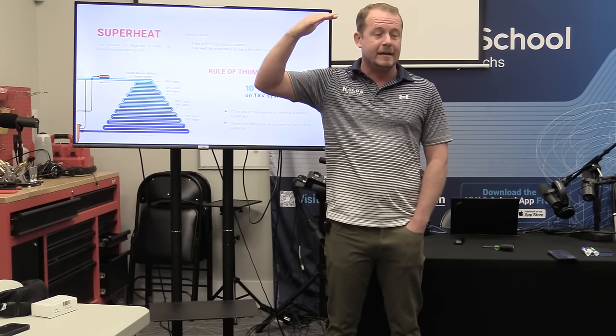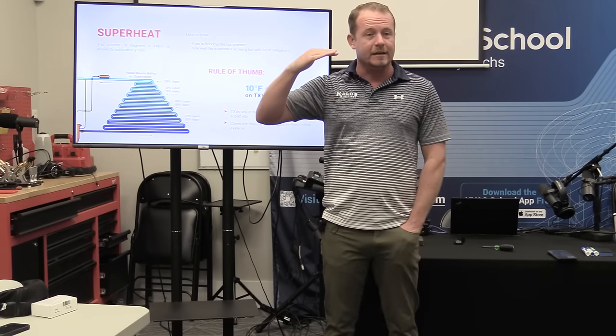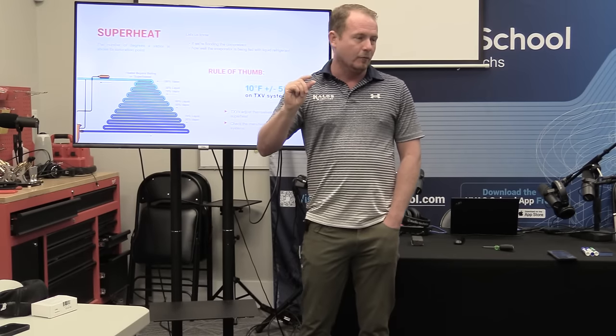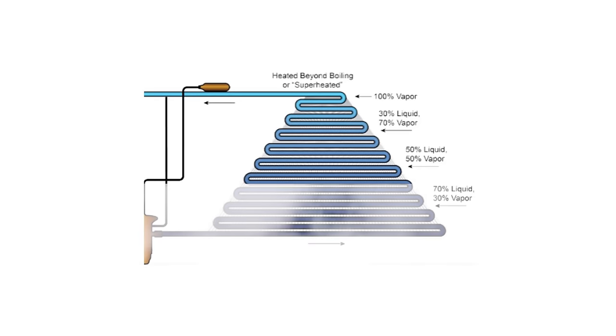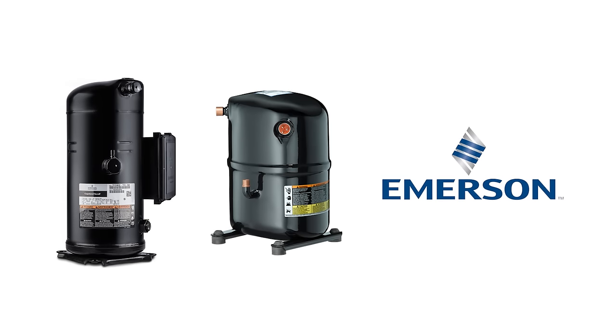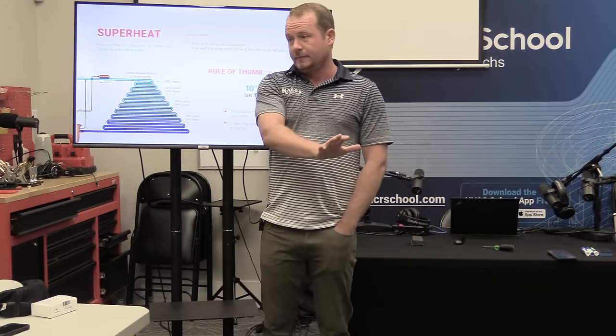Is 6 or 7 more or less efficient than 12 or 14? It's more efficient. Lower superheat equals more efficient, but it also equals more risky — like engine tuners that get more horsepower but can also blow up the engine. You're running it tighter, getting more out of it, but more risky. Same thing here. The lower the superheat, the riskier we are. Emerson, the company that manufactures Copeland Compressors — the most common compressors — wants 20 degrees of superheat at the compressor.